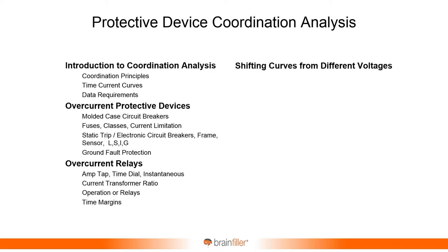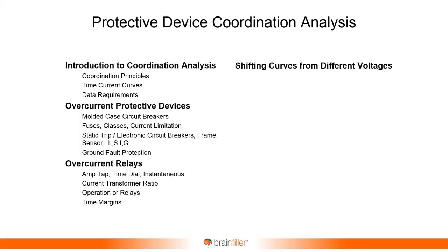We'll look at something known as shifting curves for different voltages. When you have overcurrent devices at two different voltages — such as a primary device and a secondary device on a transformer — they're seeing two different currents. It's more complex to evaluate which one would trip first. You can't just compare the two time current characteristics directly because they're seeing different currents. I'll show you how to address that — it's called shifting the curves, which I sometimes refer to as apparent coordination.